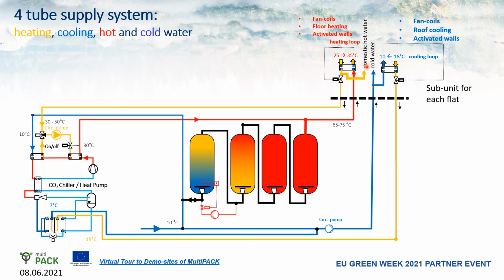and returning the water back to our heat pump to be reheated. If hot water is tapped, it is also taken from this loop. By doing so, we can maintain the heat demand for each flat individually. On the opposite side, we can cool with the cold water circulated in the building, and we can utilize the heat pump chiller to cool again, to take out this heat from the air conditioning into the hot water. This is one way to implement heat pump chillers with an efficient hot water storage, a very low capital intensive way to distribute and to be able to monitor and calculate the energy demand on each subunit individually for the flats of the building or hotel rooms or whatever it is.